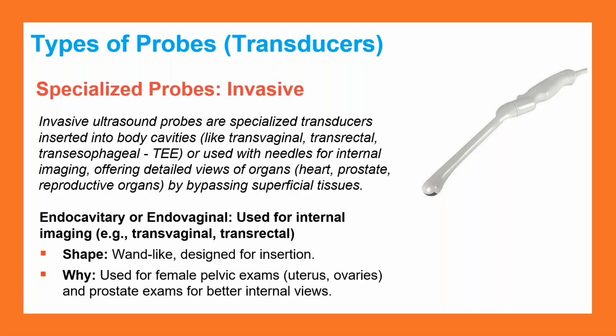One of the things we've run into a lot on these types of probes is damage to the lens, because a lot of hospitals and medical imaging centers have transferred to using a trophon or a trophon-like device, and it's caused a lot of damage, especially to the lens material and the cap. When it's a 3D, 4D probe, the cap will get loose and start leaking fluid, and you'll get image quality issues. So you really need to pay attention to your lens material and your 3D, 4D probes if you're using a trophon.